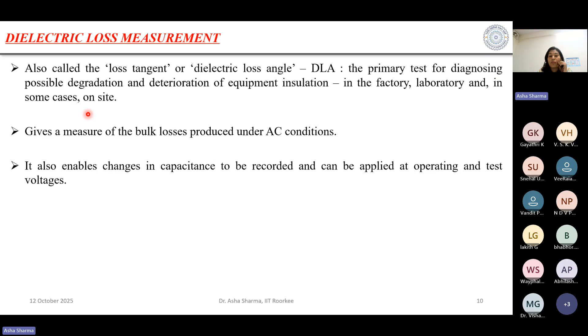If I want to measure the dielectric loss for this insulated string, it will be connected in this arm. This Rx and Cx represent the equivalent representation of my insulated string. This Cn is called the standard capacitor, and it is a gas filled type. R4, C4, and R3 are the variable resistors.